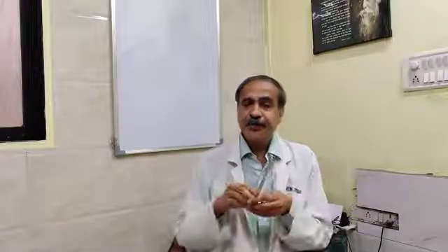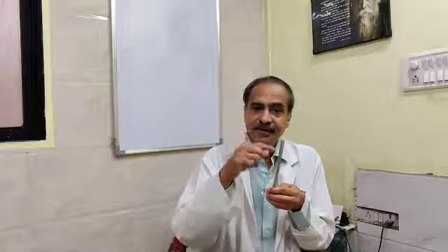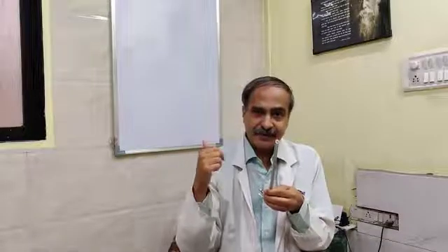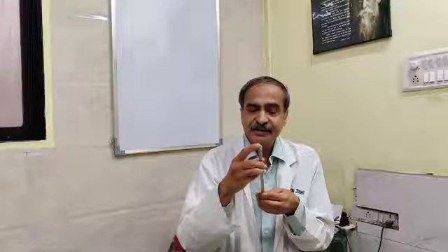Now, whenever the current is passing from the tissue, then the interior and then back, it is important that the sheath, which is the resectoscope sheath, has the insulated end.